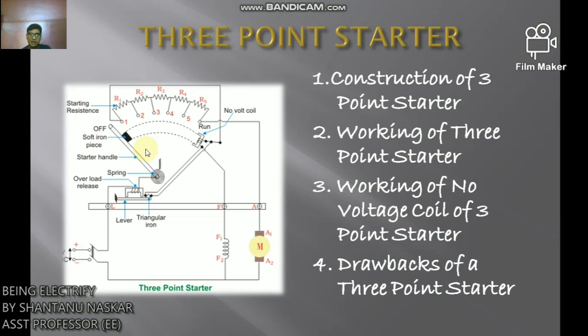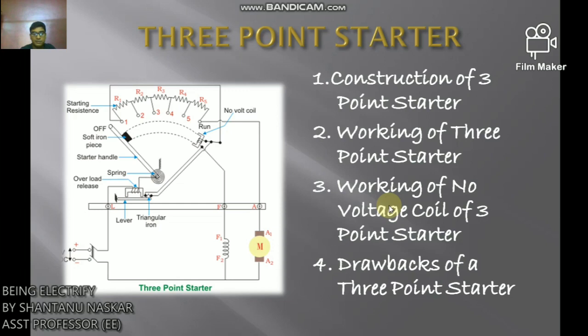The three-point starter suffers from a serious drawback for motors with large variation of speed. By adjusting the field rheostat to increase motor speed, field resistance is increased, so current through the shunt field is reduced. The field current becomes very low, resulting in the holding electromagnet being too weak to overcome the spring force. The holding magnet may release the arm of the starter during normal motor operation and disconnect the motor from the line. A four-point starter is used instead, which does not have this drawback.